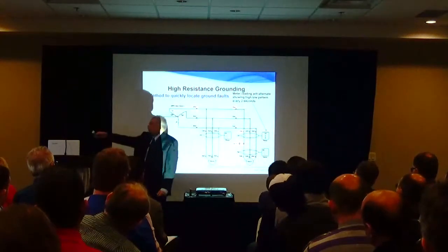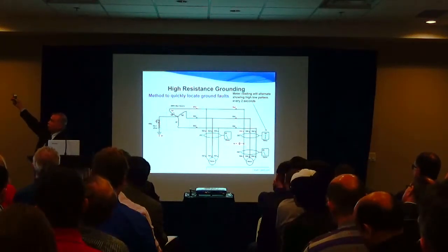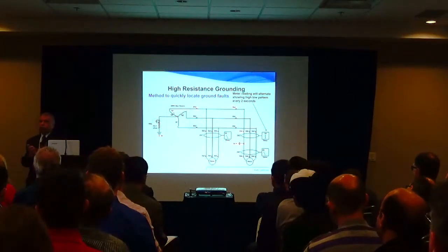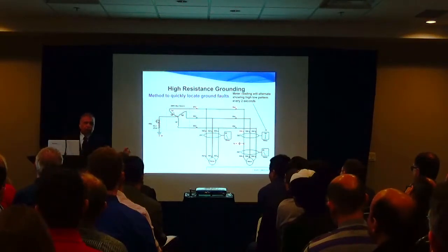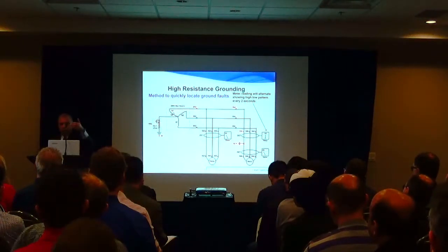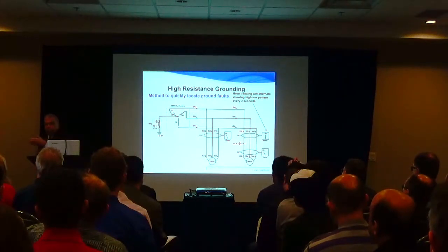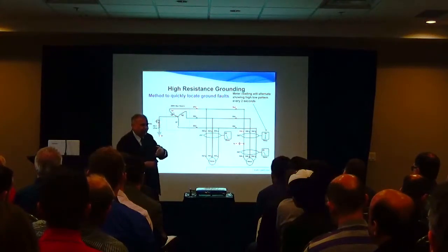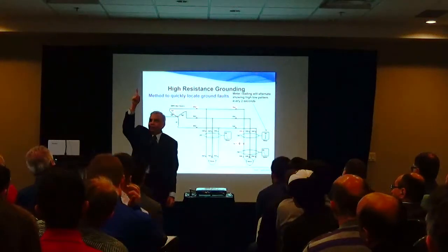If there is a panel on the side, and I recognize there is a conduit coming out, I go and look at those conduits, and I'll identify which one has a problem from the oscillation in my handheld meter. Then I go down the line where the load is and see whether it is in the load or before the load. If it is in the load, you are there. If it is not, you come back halfway and see whether it is on that side or this side. If it is on this side, you come back further halfway. So you build a series: one half, one quarter, one eighth, one sixteenth. You are truncating rapidly. In 3 or 4 measurements, you know where the fault is, right there.